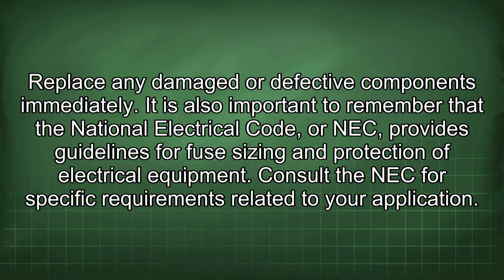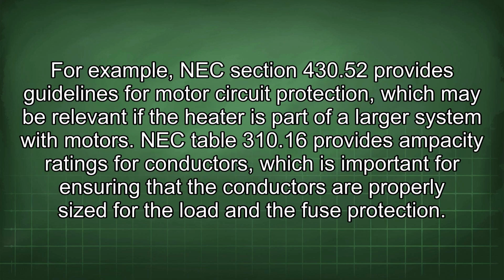It is also important to remember that the National Electrical Code, or NEC, provides guidelines for fuse sizing and protection of electrical equipment. Consult the NEC for specific requirements related to your application. For example, NEC Section 430.52 provides guidelines for motor circuit protection, which may be relevant if the heater is part of a larger system with motors. NEC Table 310.16 provides ampacity ratings for conductors, which is important for ensuring that the conductors are properly sized for the load and the fuse protection.